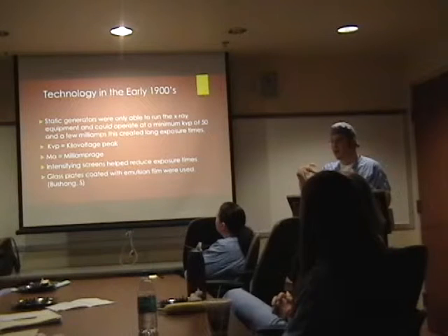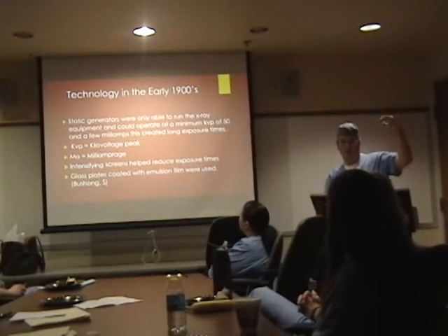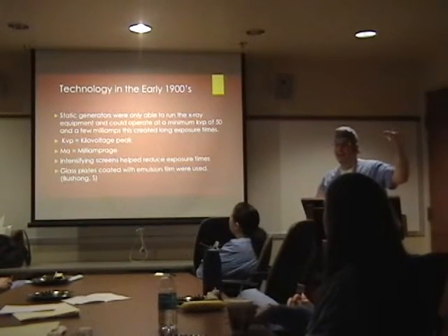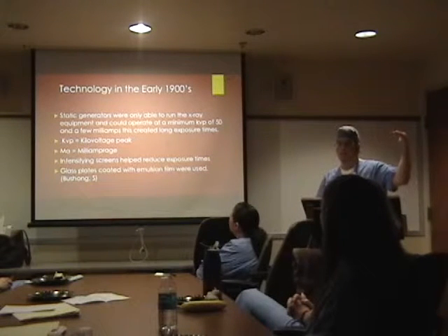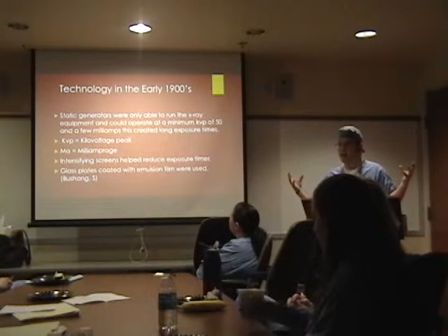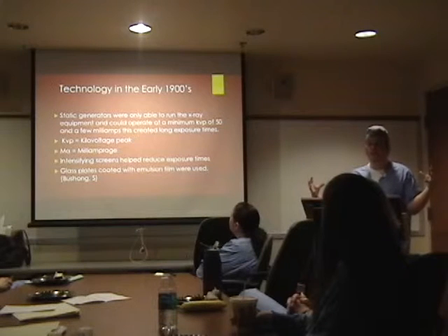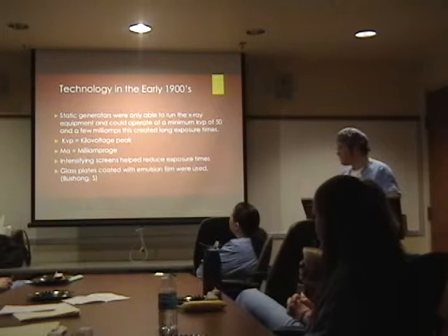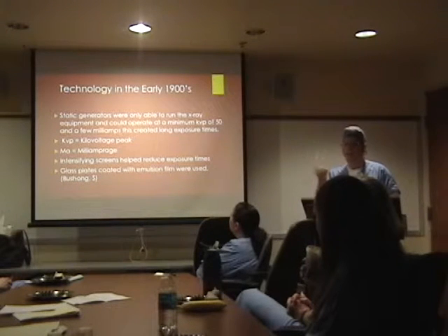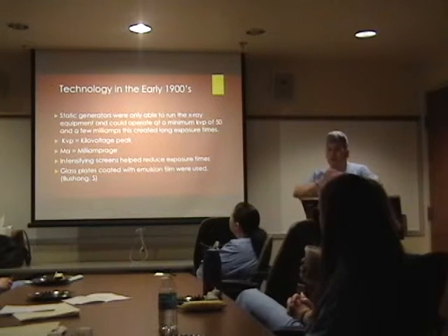Like I was saying, the equipment that we use now has a lot of kVp because you have a lot of power. 80 kVp is 80,000 volts. That's what you're putting through our x-ray tube, so that's why it gets so hot. We're operating at 80, at 125. That's a lot of voltage. Milliamperage is quantity: how much energy do you want to send down?